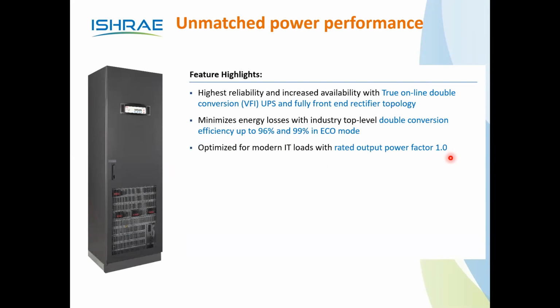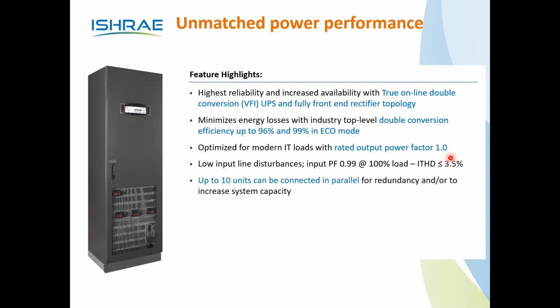This technology is not available with only one supplier. All the manufacturers have this output power factor. But unless we specify that we need only unity output power factor, we may not get it. So let us go toward the better technology. And the THDI will be 3.5% since it is using a diode with IGBT. Up to 10 units can be paralleled at maximum. Integrated manual bypass and optional backfeed protection.